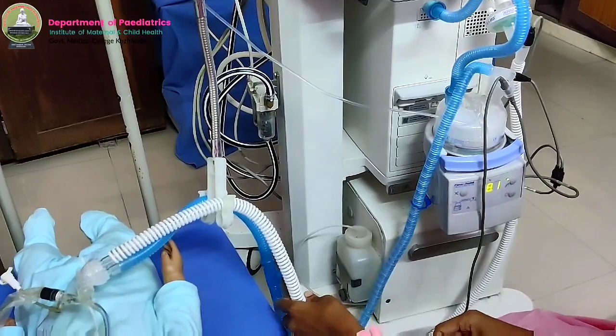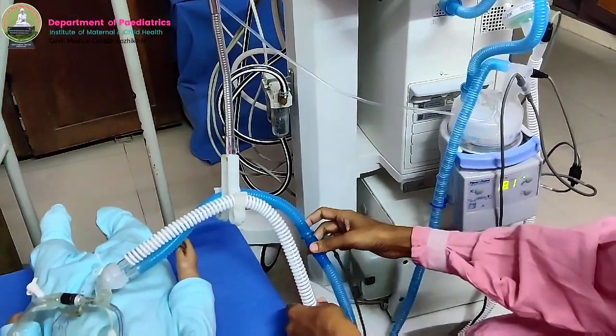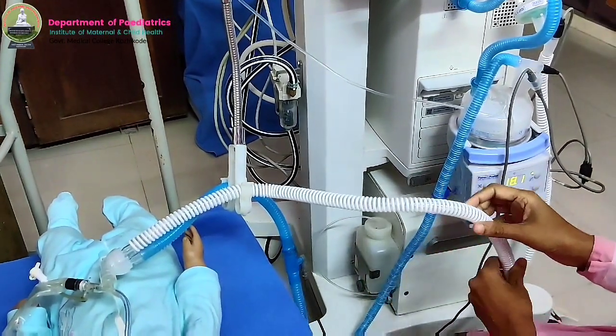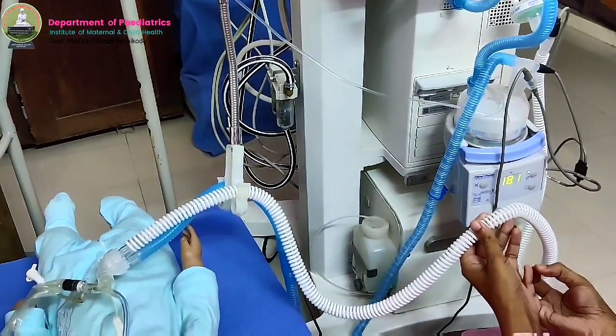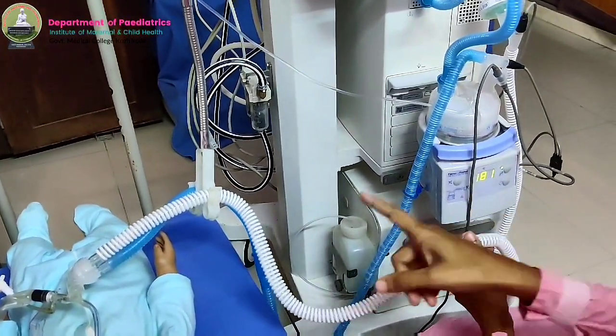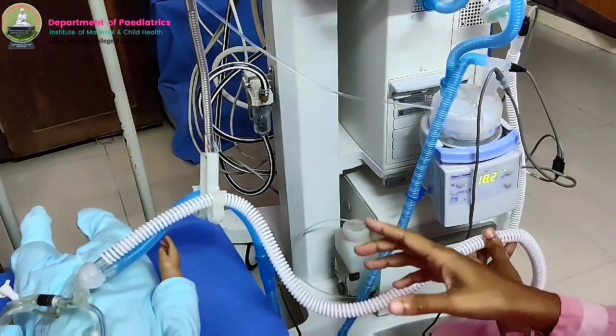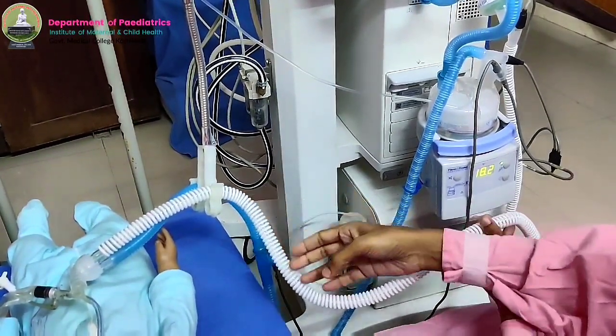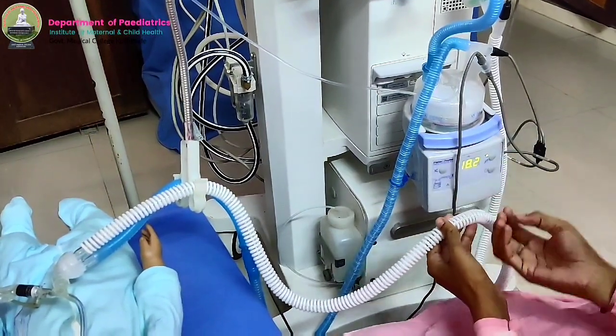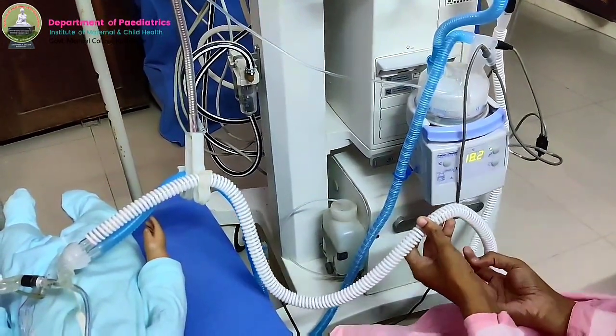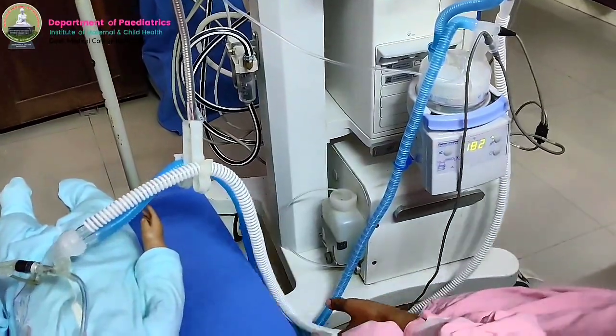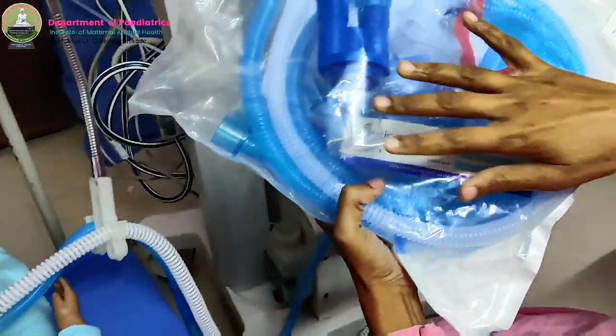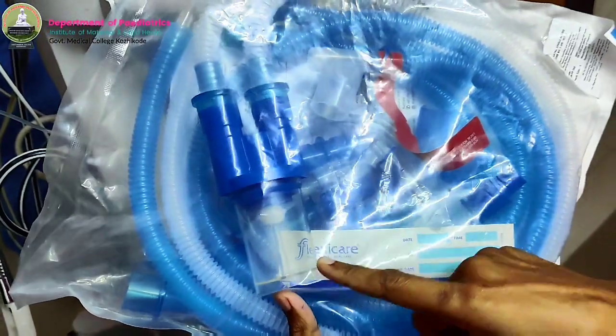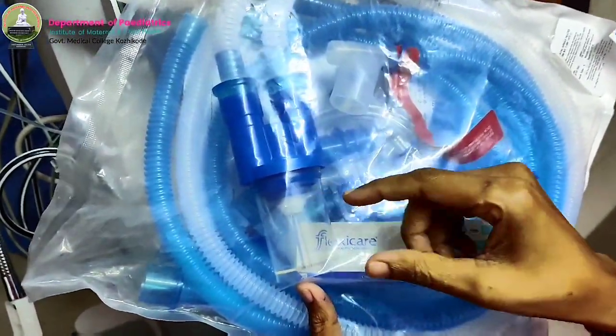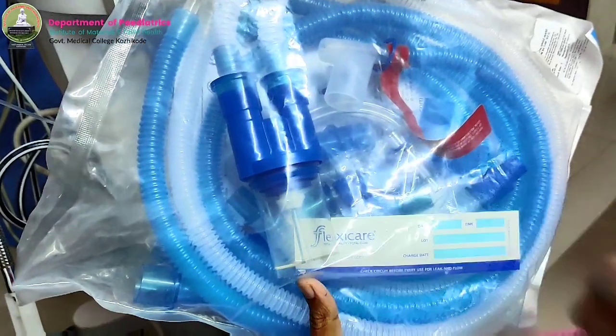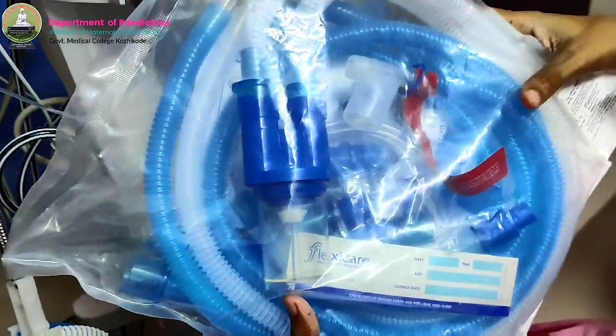In some ventilators, only the inspiratory limb will have a heated wire and the expiratory limb will have a water trap in it. What is the use of that water trap? Since it does not have a heated wire, we should expect the water vapor to condense, and that can be collected in the water trap in the circuit. So this is such a ventilator circuit. You can see the water trap. When this gets filled up with water, we have to open the cup, remove the water, and fit it again properly.